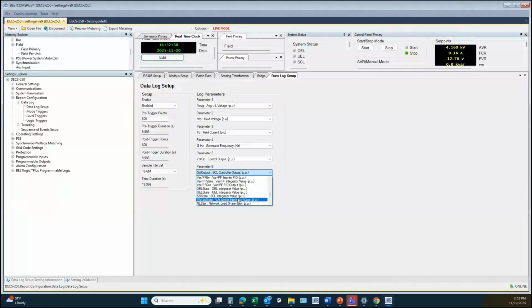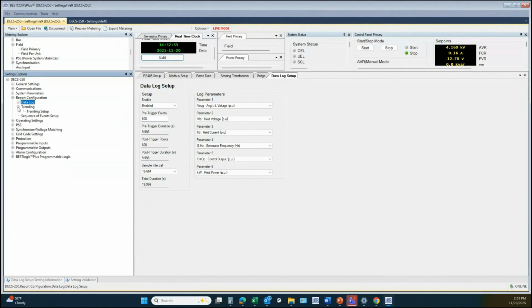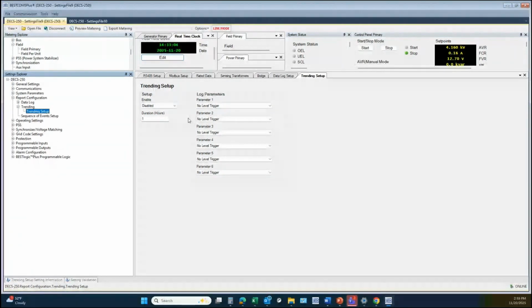And then the final one could be KW, for example, or maybe instead of control output, you want kVAR, your reactive power. That's how you would set up the data log. Trending, I'm going to skip through that, but that is essentially the same thing. It will record an event, or actually it's recording a duration, and the same 6 parameters can be used.